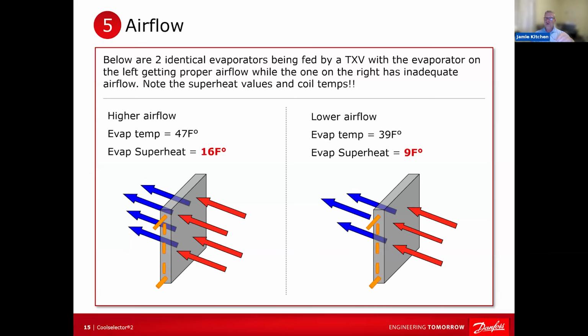Now remember, the only way for the compressor pumping to balance the TXV is for that evaporator pressure to drop as well, because that reduces the pumping capacity of the compressor until it matches the lower feed rate of your TXV. So look at this, 39 degrees, right? You may think, holy crap, I'm undercharged. No, you're not. Look at your superheat, 9 degrees. That's a reflection of how open your TXV is. So your TXV is opened a lot under good airflow, high load, perfect. It is less on low load.